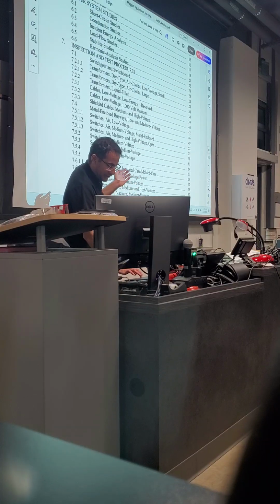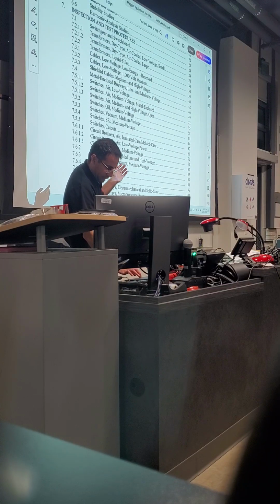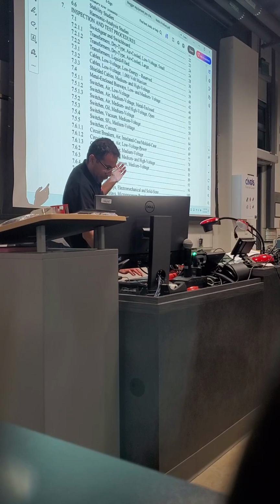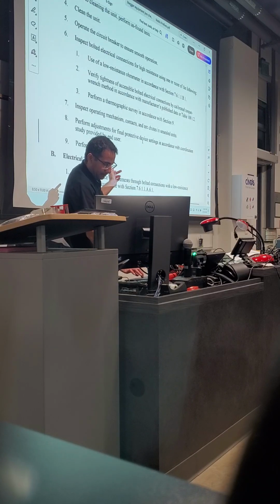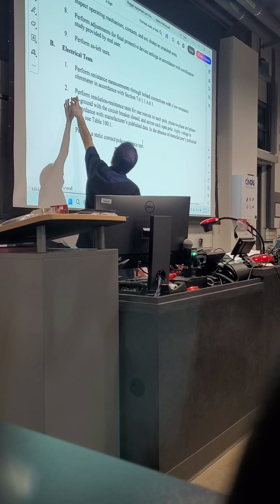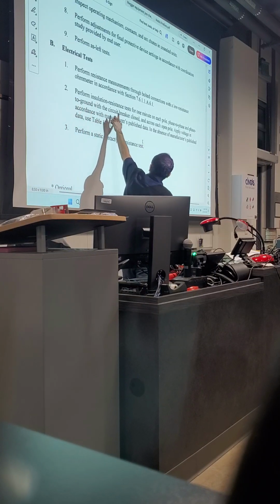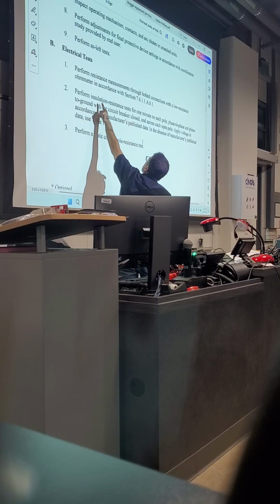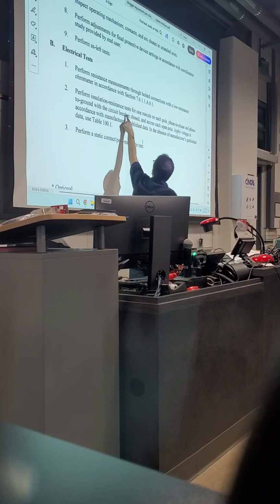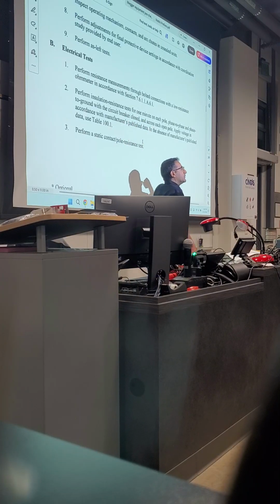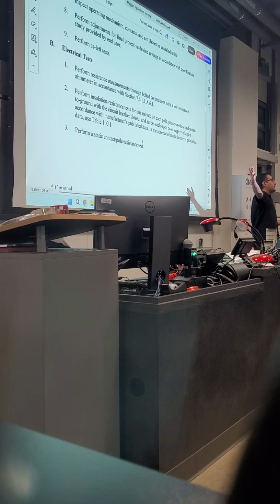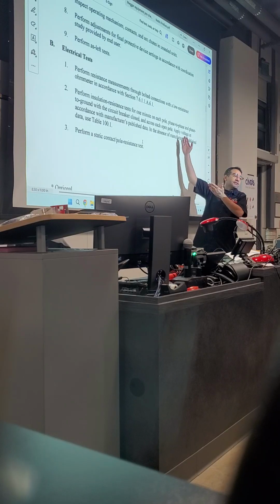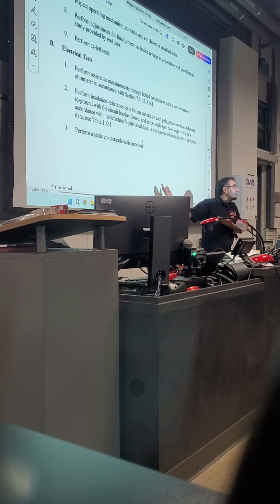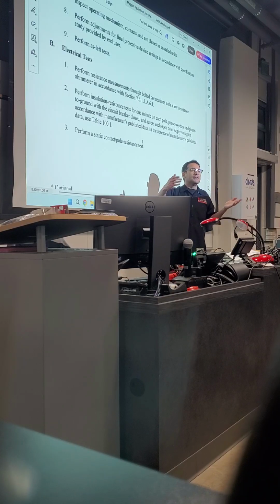Perfect. We go back to section 7.6.1.1, molded case circuit breaker. And electrical test. This is a megger. Item number 2. Perform insulation resistance, aka megger, for 1 minute. So this is according to standard. You can do it for 2 minutes, you can do it for 30 seconds. I'm not going to make any comment on that. My responsibility is to show you the right way. 1 minute. So you're going to run it for 1 minute.